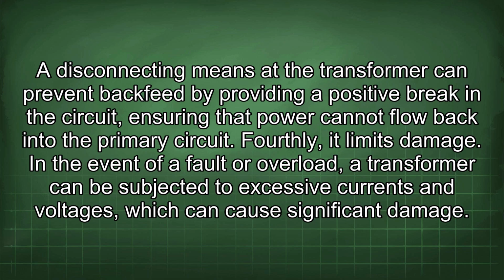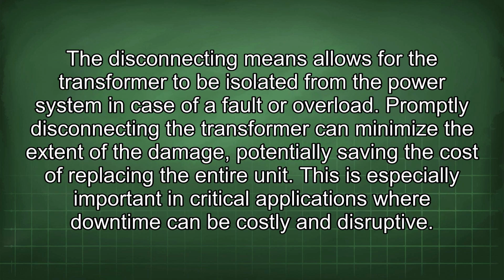Fourthly, it limits damage. In the event of a fault or overload, a transformer can be subjected to excessive currents and voltages, which can cause significant damage. The disconnecting means allows for the transformer to be isolated from the power system in case of a fault or overload. Promptly disconnecting the transformer can minimize the extent of the damage, potentially saving the cost of replacing the entire unit. This is especially important in critical applications where downtime can be costly and disruptive.